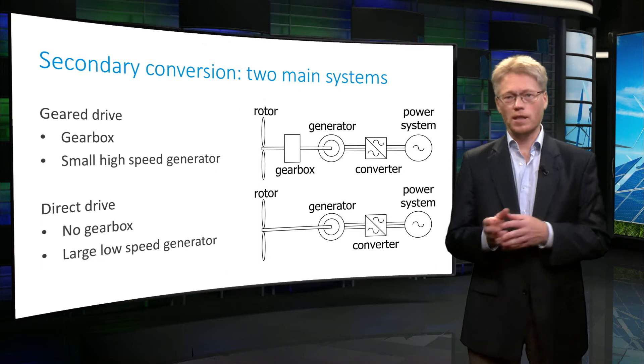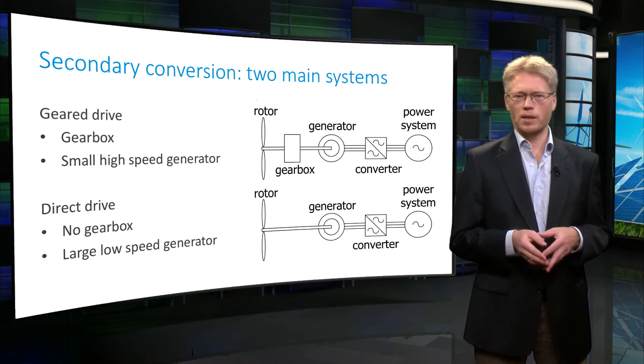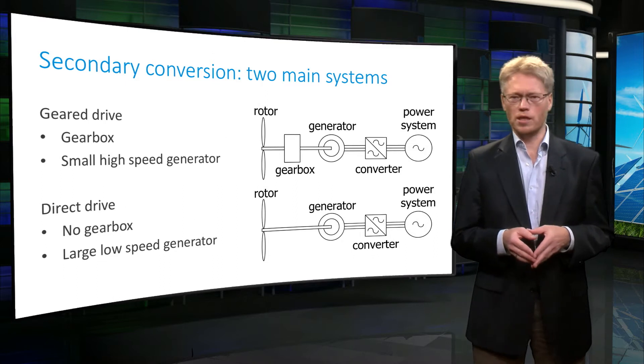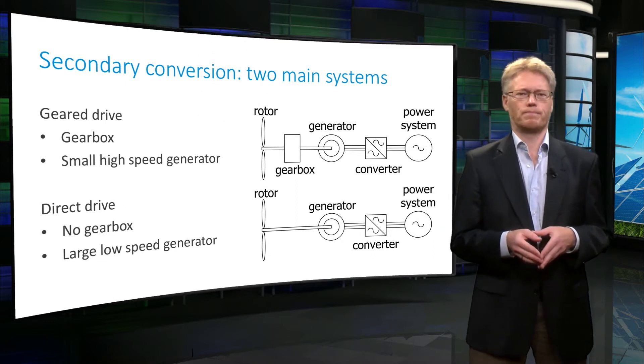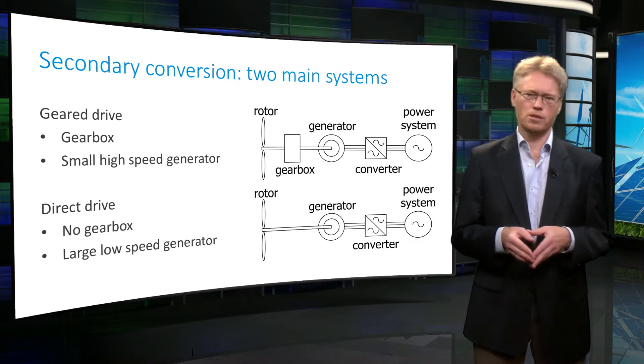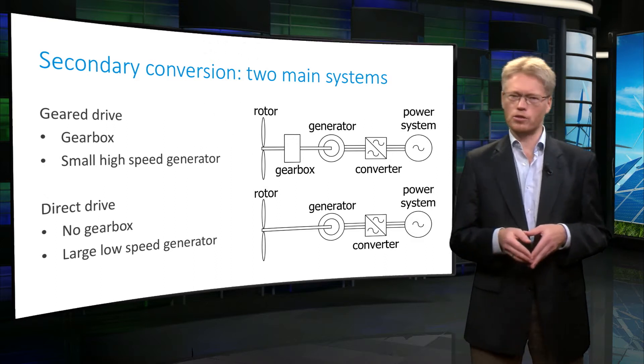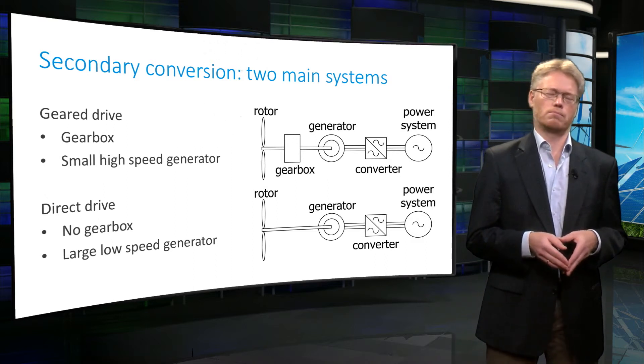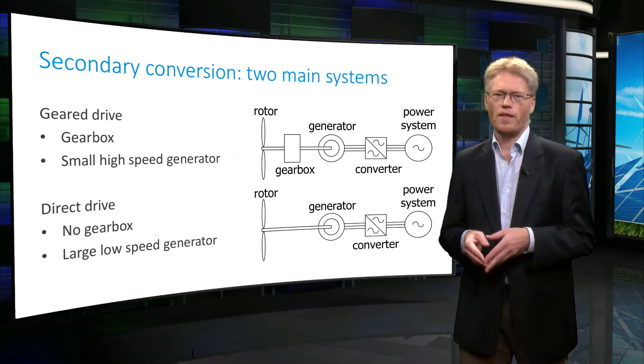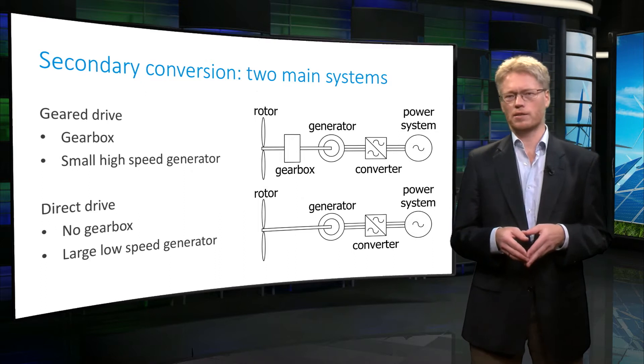In a direct drive system, the generator is directly driven by the main shaft of the wind turbine, so it rotates at a very low speed. The most important reason to develop direct drive systems is to get rid of the maintenance and failures of gearboxes. However, the consequence is that a large and expensive direct drive generator is needed.